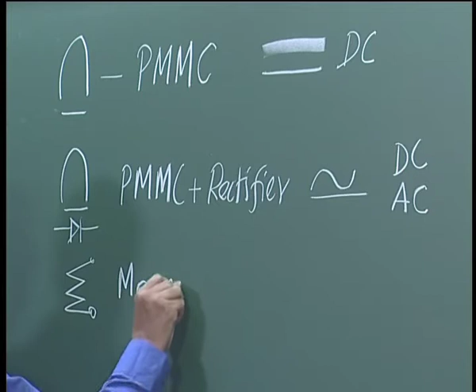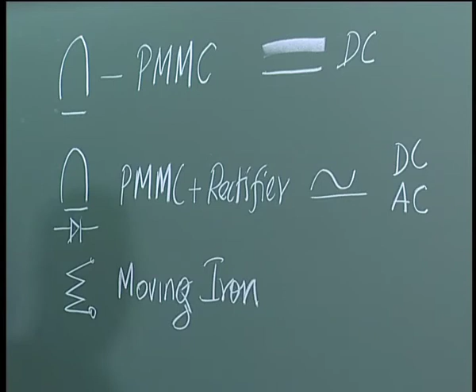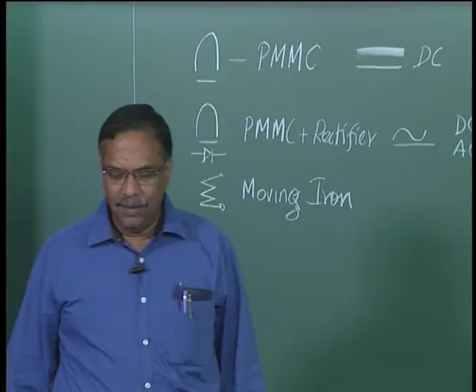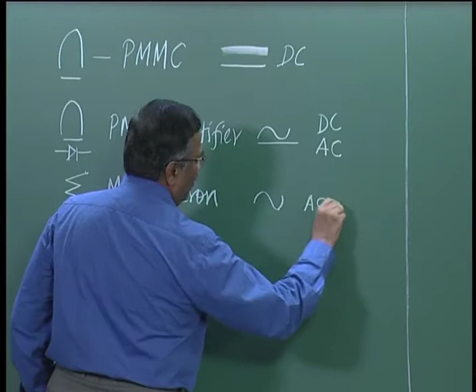If you see this symbol, the manufacturer is telling you the meter is moving iron type. Some moving iron meters are only for AC, and some manufacturers make them for both DC and AC. If it is only for AC, you will see only this symbol, meaning AC only. Of course, moving iron meters will also have a symbol for both DC and AC.